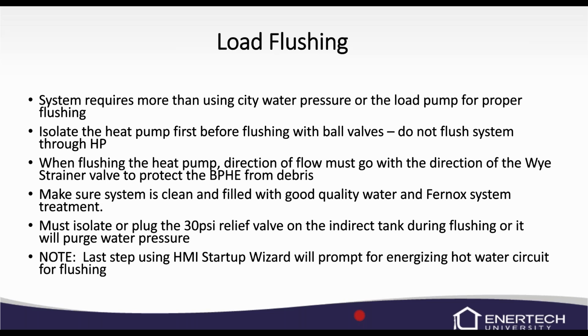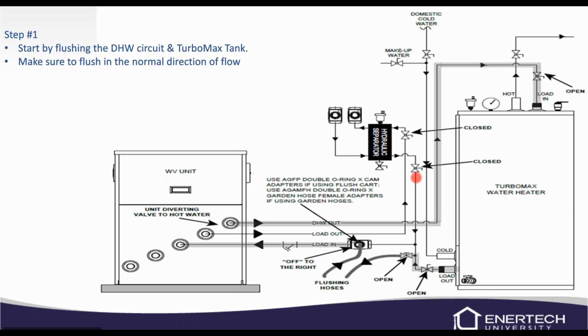The last step when you're flushing is you're going to have to send power to the unit, and we're going to have to go into the startup wizard, because we're going to have to energize that three-way valve and switch it so that we can flush the hot water circuit. We're going to start by flushing the domestic hot water circuit and the TurboMax tank.